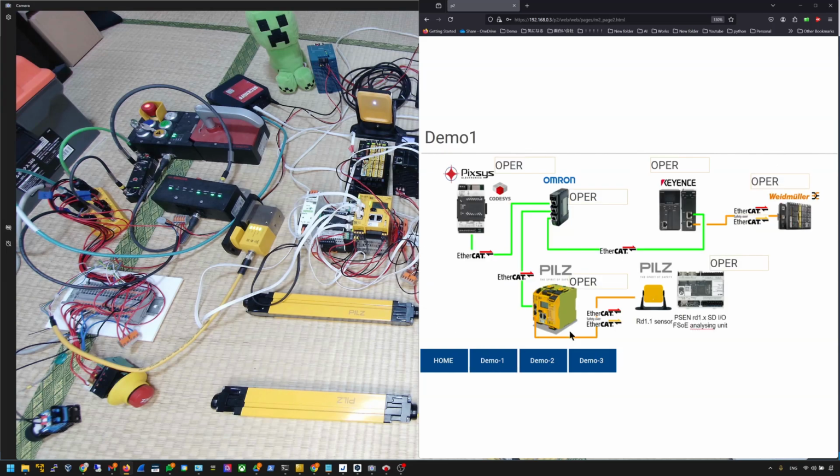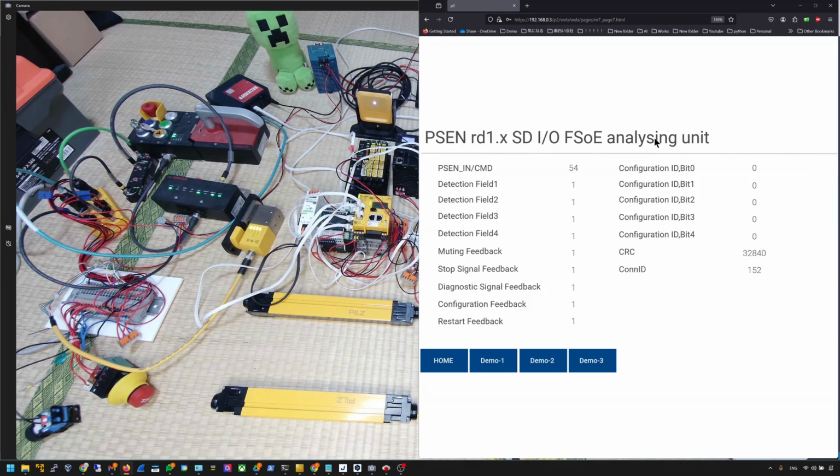And also in here, here is the ladder. Then you can see that it's also communicating. Let me put my hand in there. Okay, because for testing, I set the detect area very close. But you know that the other data can come back as feedback, and you can know if an operator is putting their hand into a working area or something.